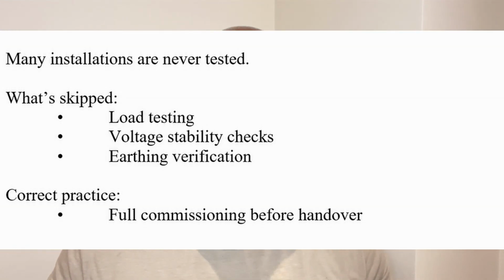Generators are not plug and play appliances. Most generator disasters that happen are not equipment failures per se, they are installation failures. It's rare for a generator bought from a reputable source to fail. Normally the failure is around the installation. So if it wasn't professionally designed, installed, tested and commissioned, it's a risk, not a backup.